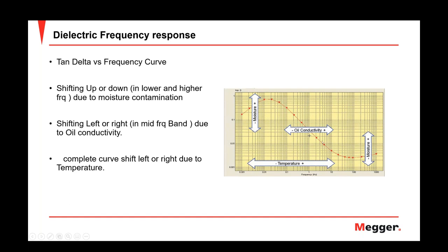Similarly, in the medium frequency region, there is a shift left or right that depends on oil conductivity. More conductivity — meaning worse oil — shifts the red curves to the right side. More to the left means drier oil with less conductivity, which is better oil in terms of insulation.